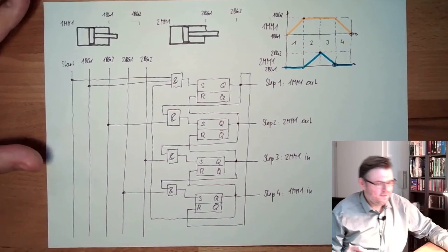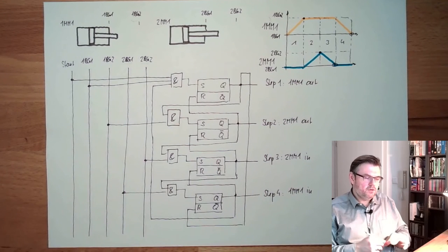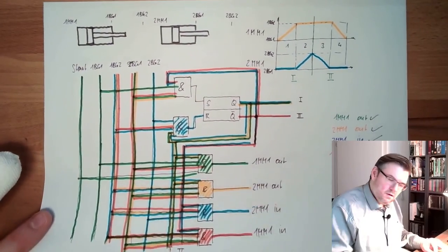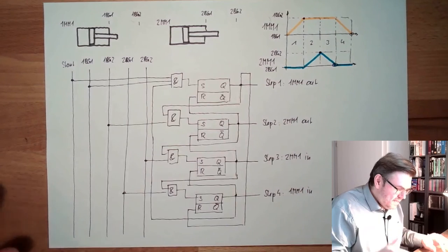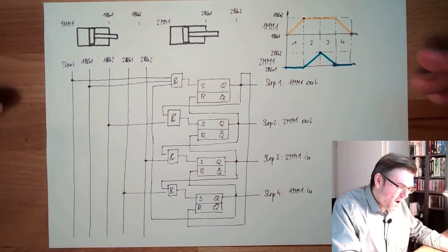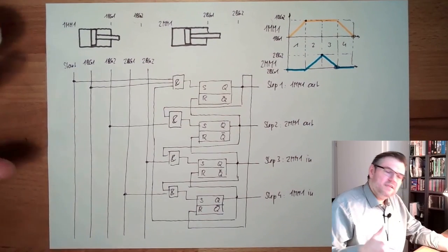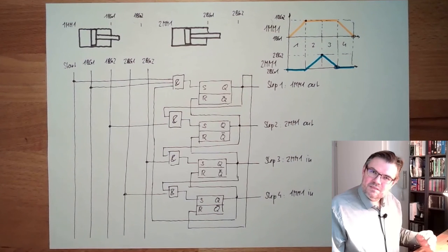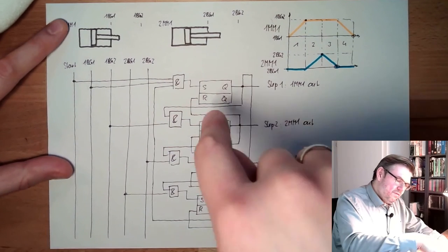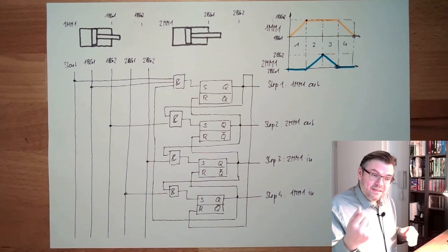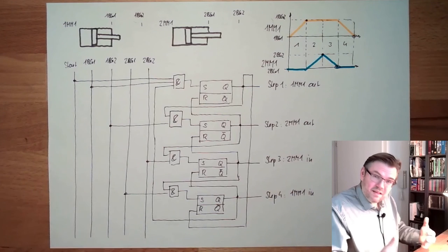So this is a very straightforward approach, you see? We don't have to use this colorful picture from last time, where in the end nobody knew what happened. We see it one by one. See step number two, step number three. It's very straightforward, and it's extendable, simply extendable. So we always have a step, we have a transition to go to the next step, and the next step will reset the previous step. This is exactly like in the GRAFCET.